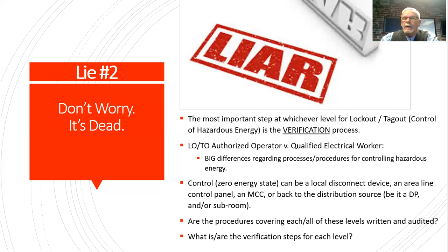One of the more common things that I do come across is the program folks. A lot of things today, the machinery, we have different logic drives, we have PLCs, we have other methodologies. And invariably, you walk down an aisle, there's a cabinet that's open, there's someone, ironically, sitting on a folding metal chair with their laptop on their lap, and they're just programming away. The cabinet is a two-sided cabinet. Usually the right side, as you're looking at it, is the power side. If it's a line drive setup, you're going to have high volt. Well, you're going to have 480 volts in that side. OSHA considers anything at 600 or above high voltage. NFPA 70 says we kick in at 480.